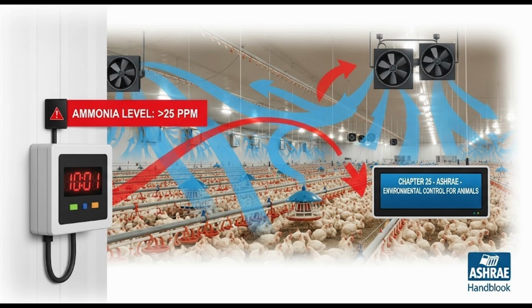That's uncontrolled air coming in from who knows where, bypassing the proper inlets and potentially disrupting the planned air distribution pattern. It really highlights why building air tightness is so important for controlled ventilation to work properly. That makes sense. Control the leaks so your controlled inlets do the work. Exactly. And finally, the handbook covers fan selection, getting the right type and size, and different ways to control the ventilation rate as conditions change. Simple on-off timers, staging multiple fans, using multi-speed fans, or variable speed drives linked to sensors for temperature, humidity, or even gas levels. Okay, that's a pretty comprehensive look at the animal side.